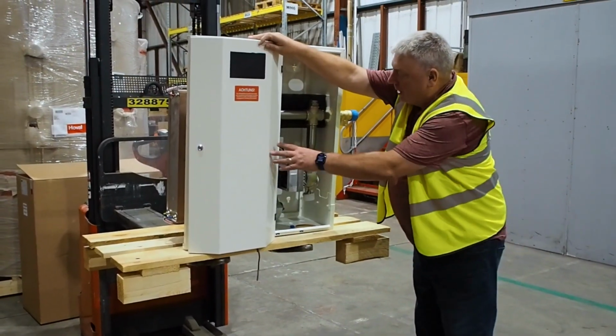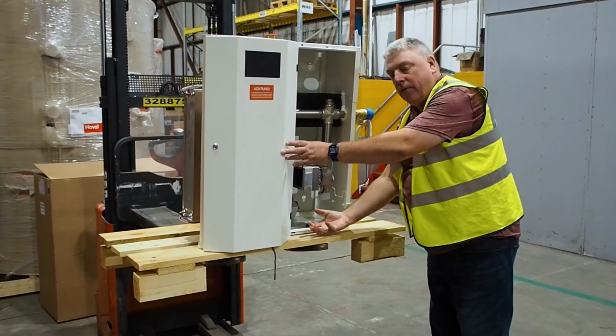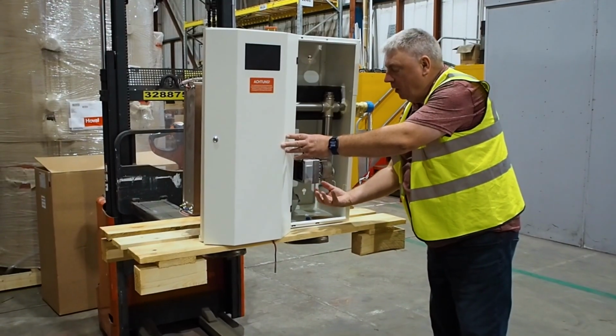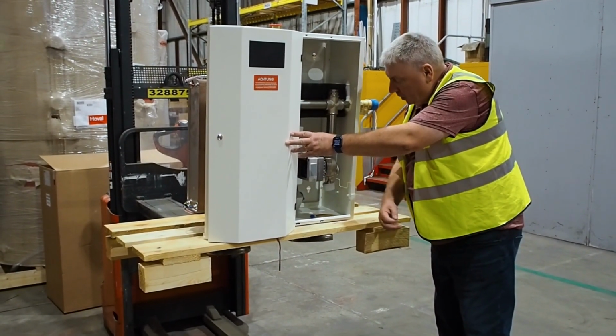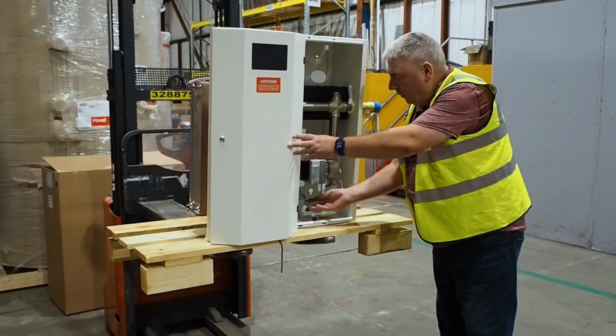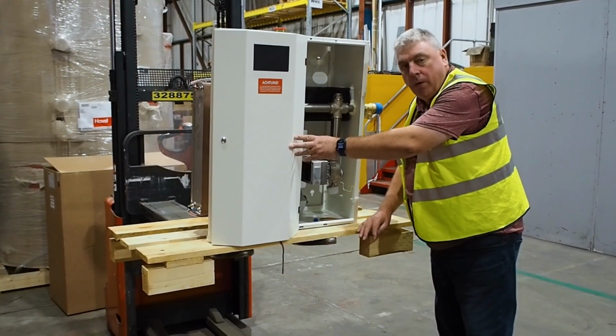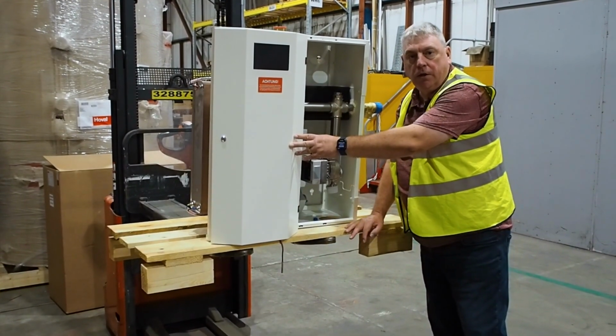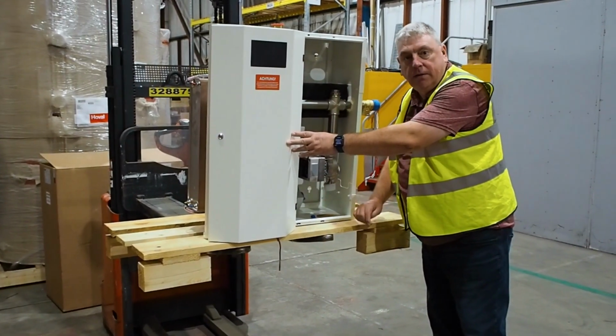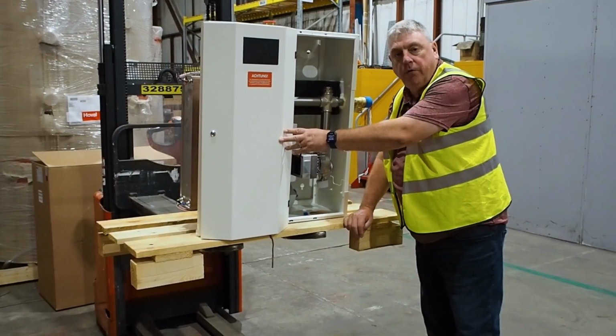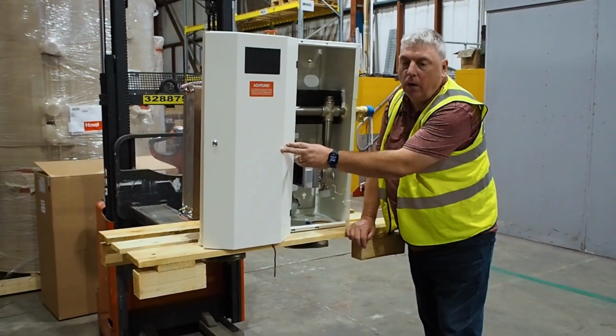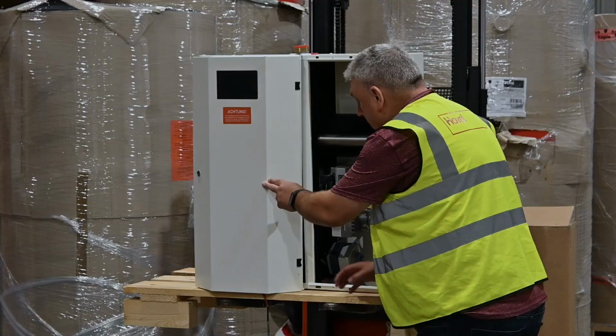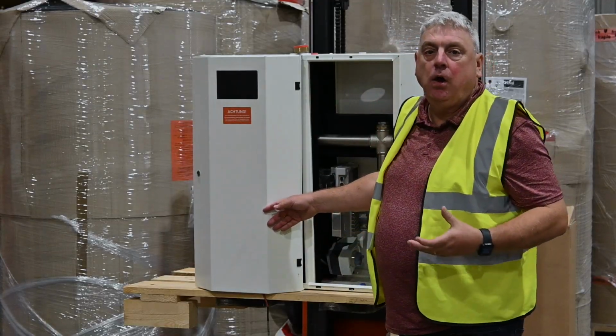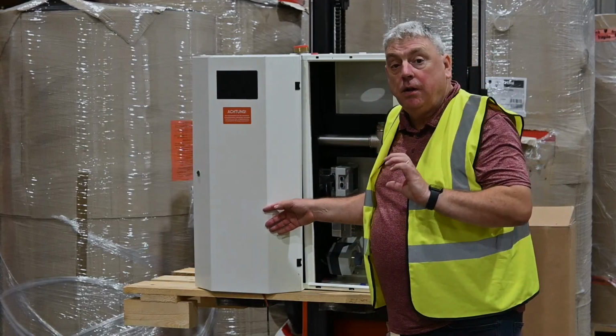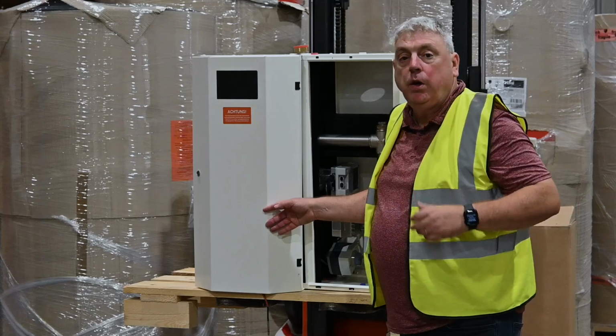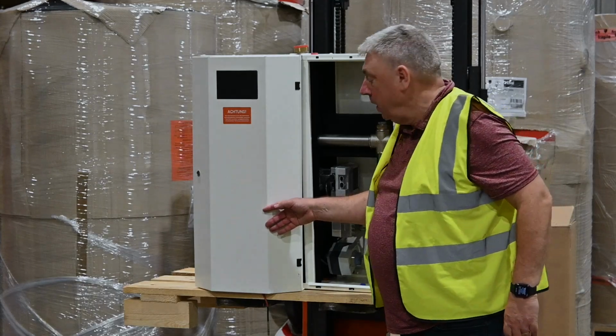Okay, primary side, we again would have to imagine connections coming from the boiler going in at the bottom, through the 3-port valve, and then through the pump, and then on to the plate heat exchanger, before going back down again and out to the return of the heat generator, the boiler or the heat pump. And again, that will have a commissioning or a balancing valve on it, so that the flow rates can be all set when we come to commission the equipment on the site.